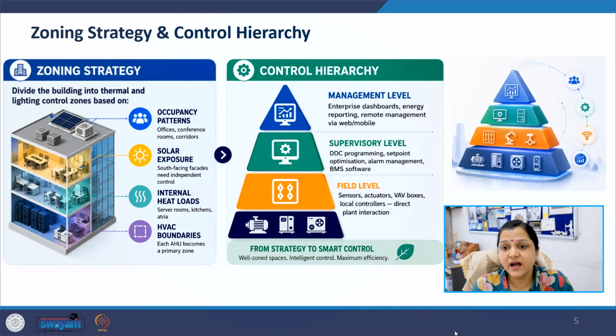The zoning strategy and control hierarchy. A building should never be controlled as one large space. Instead, it must be divided into different zones. These zones are created based on occupancy pattern, solar exposure, internal heat loads, and HVAC boundaries. For example, a south-facing facade receives higher solar heat gain and may require independent control. Conference rooms have changing occupancy patterns, so they also require separate control. Similarly, server rooms generate high internal heat and cannot be grouped with normal office space.